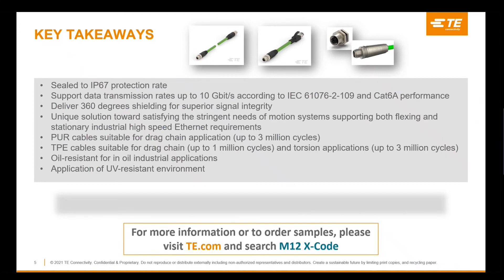M12 Xcode is a comprehensive connection technology experiencing a significant increase in interest as more companies look for higher network speeds and more reliable, high-quality data transmissions. The 8-pin M12 Xcode design is the most recent evolution in the industrial environment, supporting IP67 sealing requirements and data transmission rates up to 10 gigabits per second. Ethernet transmission speeds comply with IEC 61076-2-109 standards for CAT 6A performance levels, designed using 360-degree shielding technology for superior signal integrity.